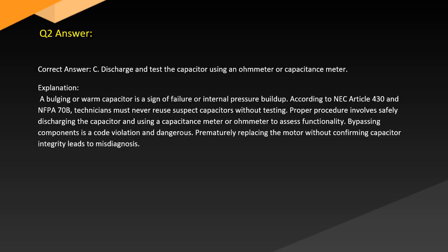Answer. Correct answer. C. Discharge and test the capacitor using an ohmmeter or capacitance meter. Explanation. A bulging or warm capacitor is a sign of failure or internal pressure buildup. According to NEC Article 430 and NFPA 70B, technicians must never reuse suspect capacitors without testing. Proper procedure involves safely discharging the capacitor and using a capacitance meter or ohmmeter to assess functionality. Bypassing components is a code violation and dangerous. Prematurely replacing the motor without confirming capacitor integrity leads to misdiagnosis.